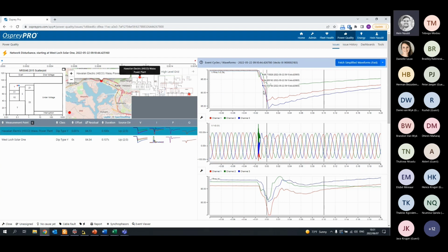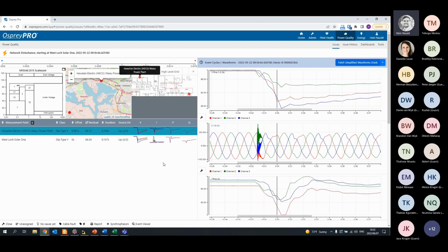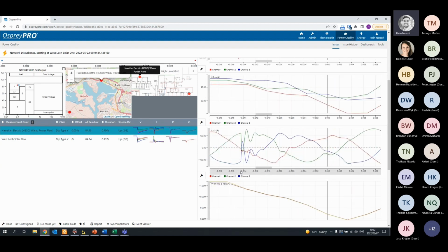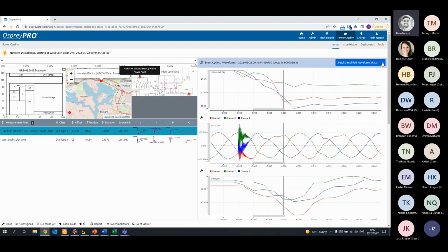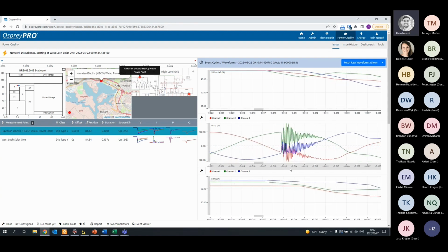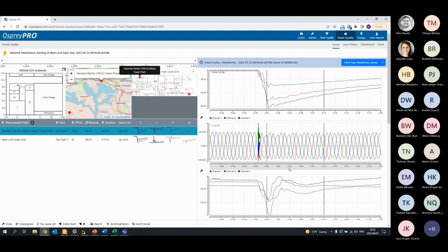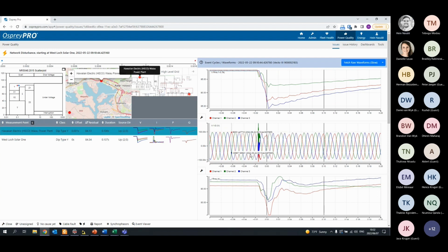If you click on fetch simplified waveforms, it will then fetch the waveform data. So that's the half or full cycle RMS data, and this is then your 50 kilohertz sample data. So it shows you your voltage, your current, how your current waveform looks during that period, and so on. Now, this is the simplified waveform. The raw waveform will give you even more samples. You can see it's also a bit slower to process. But yeah, you can get that and use those graphs as well for exporting.